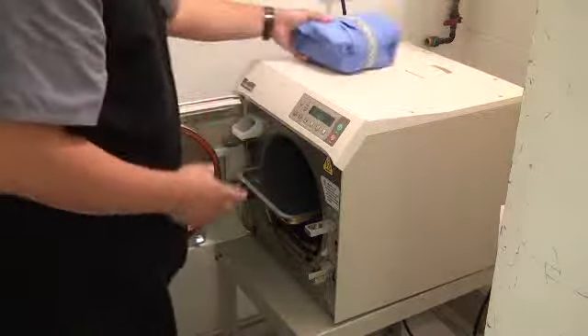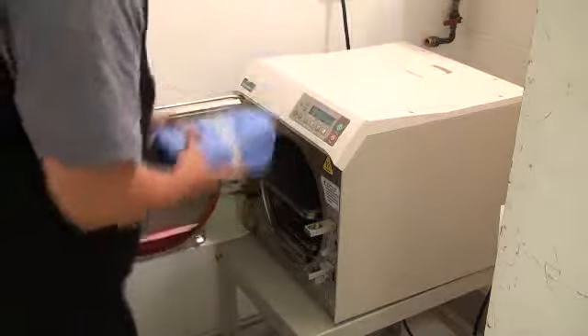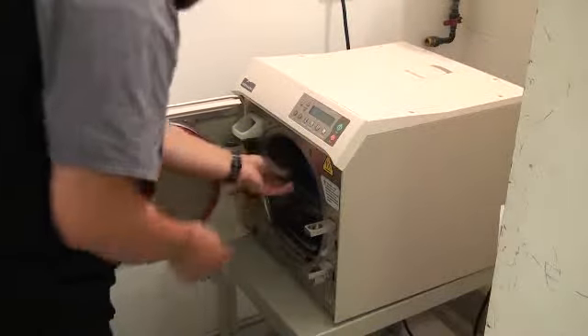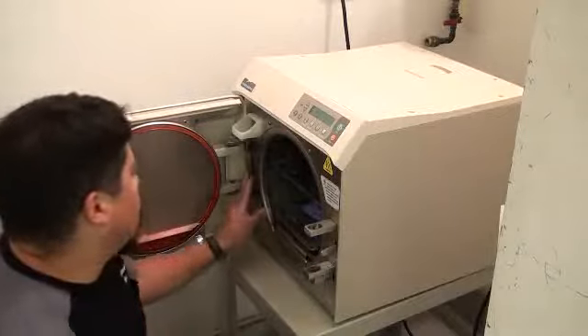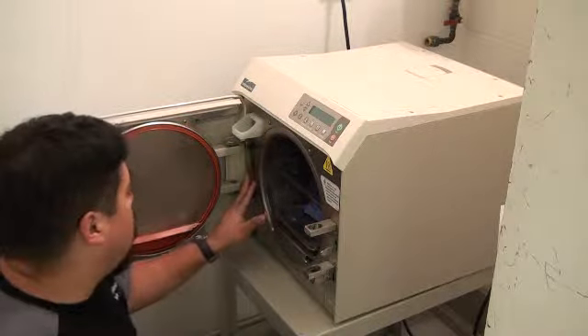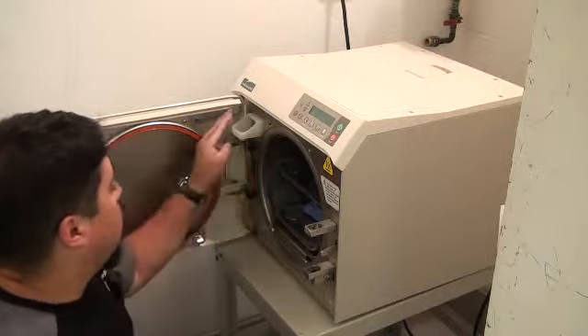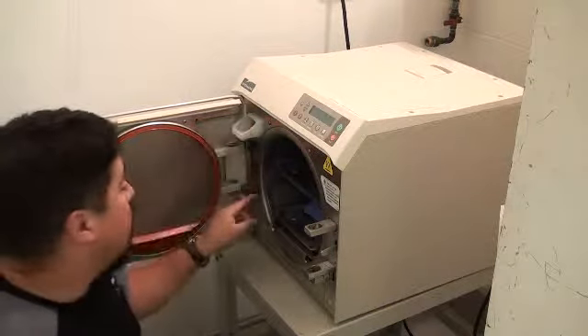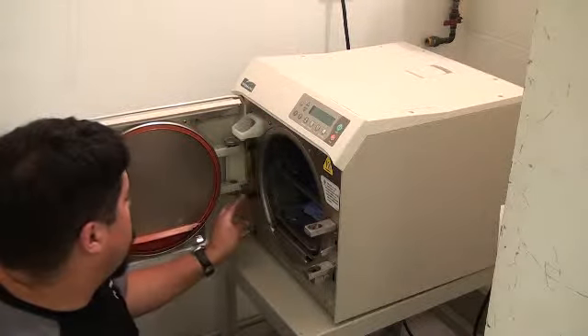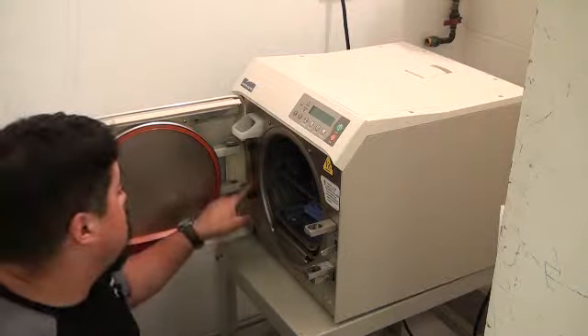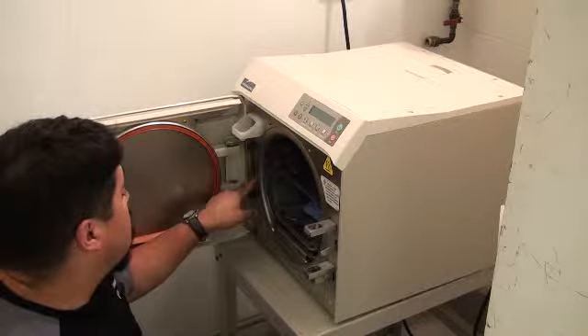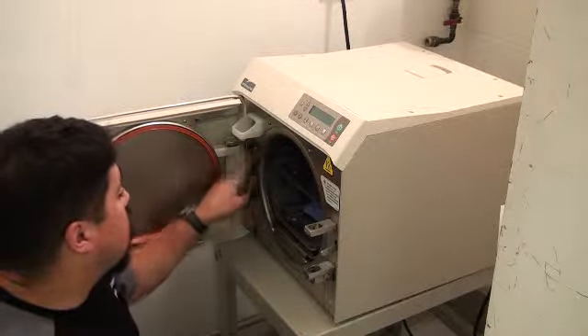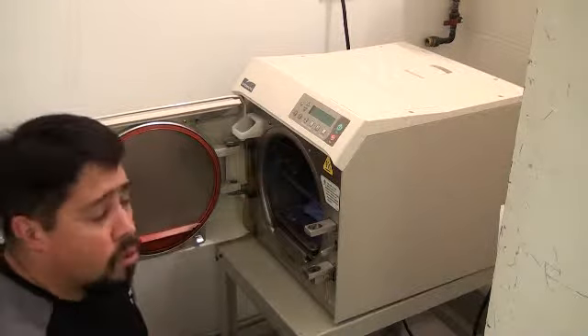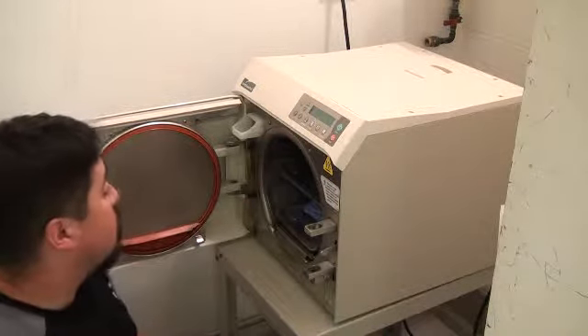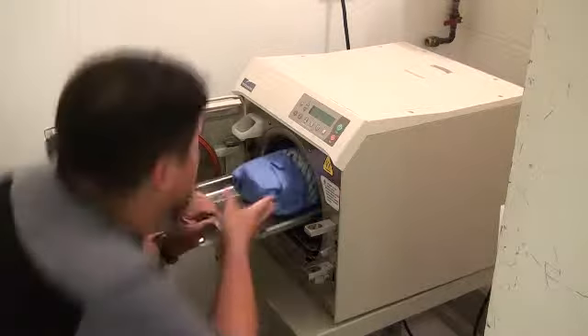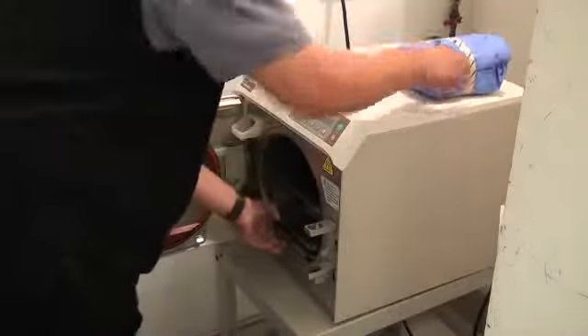Maintaining the autoclave, well, again, when you pack it, you should ensure that the water level is adequate. In this model, you can pour water, distilled water, into here, and you will have a tube here that can be used to drain water during its maintenance cycles. But as long as the water is in this green zone, you have enough water to sterilize a pack. Take these out for a moment.